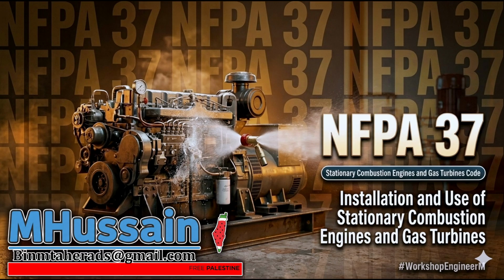Exactly. Now the owner needs double-walled piping, leak detection monitoring, annual EPA testing. Yeah. All because of the pipe. The pipe literally became the tank mathematically. It requires engineers to really look at the spatial layout holistically. You can't just look at the engine alone. Okay, so despite all of our clearances and thimbles and iron pipes, NFPA 37 knows the system will eventually fail and catch fire. Yes. And when it does, we move from containment to active suppression.